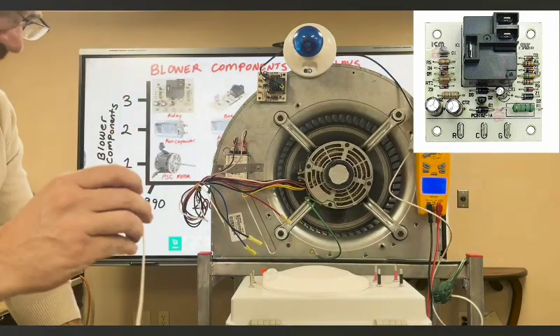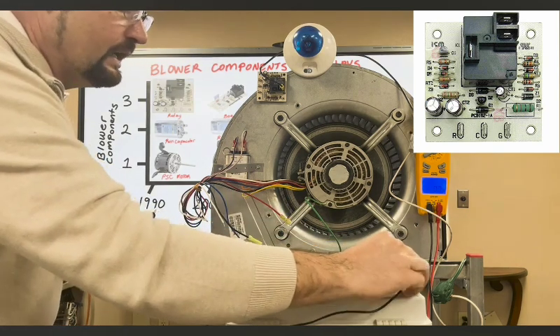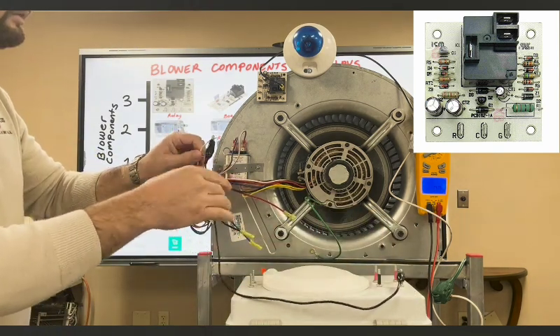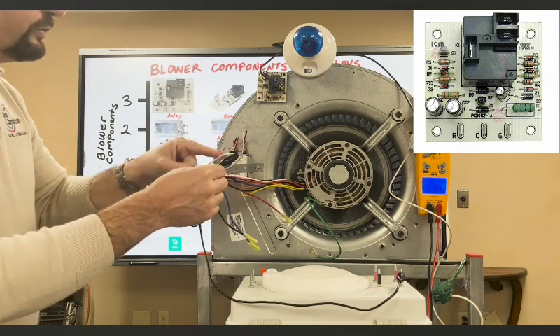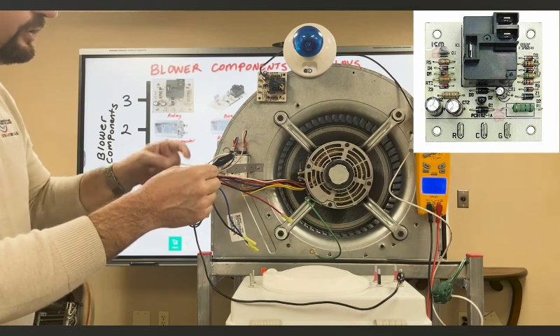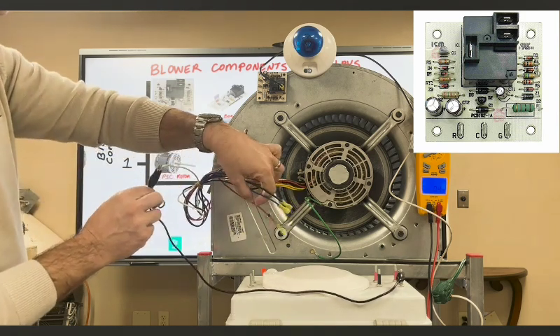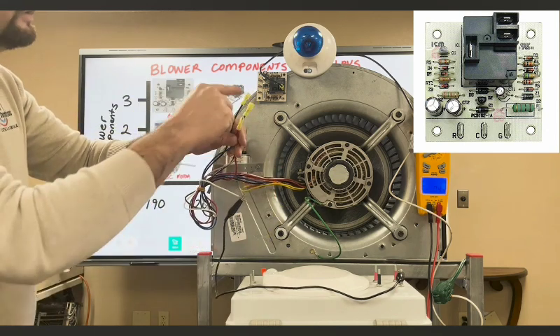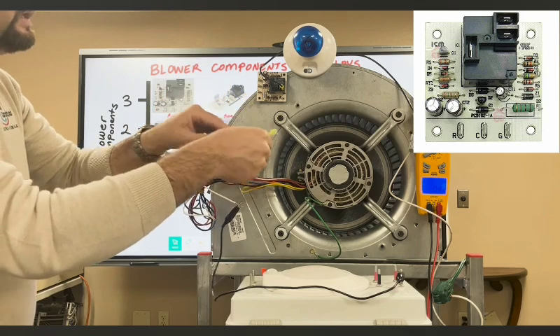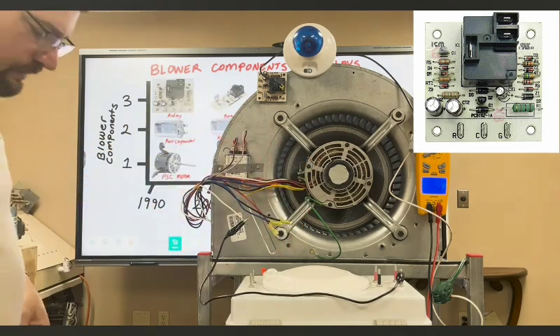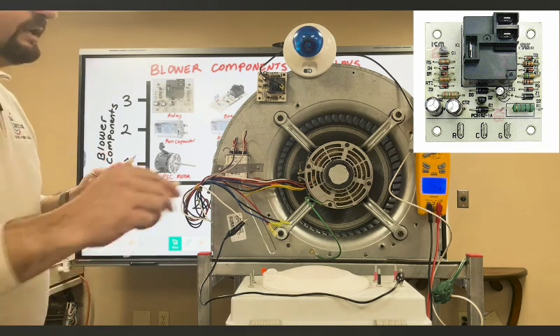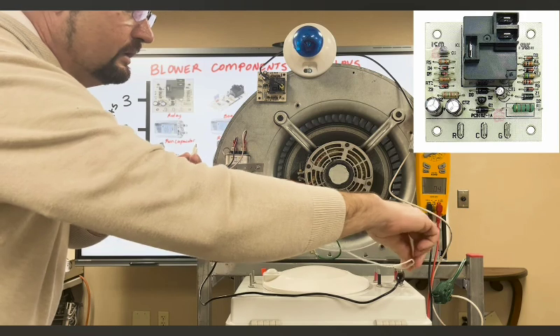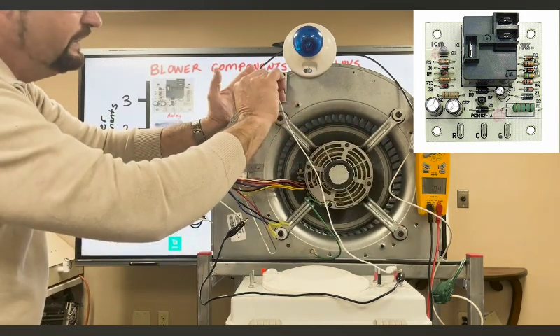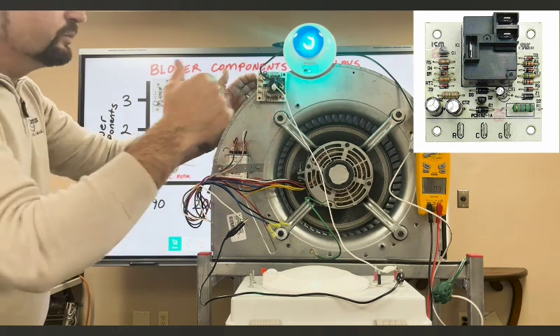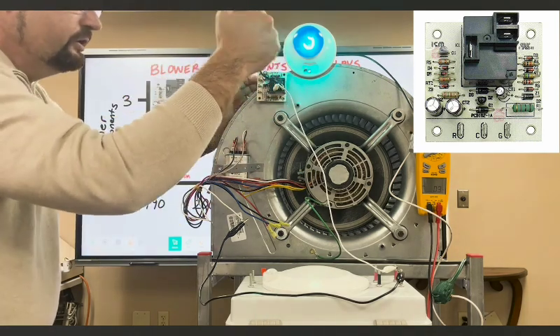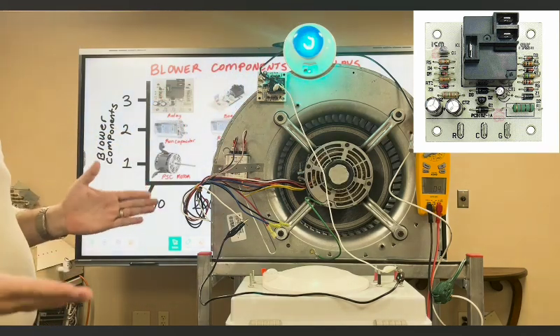Now to wire this up, we're going to take one of our lines and come up to one of our legs on our motor, which is the run winding, which has our capacitor, all that wired through to that. I have 3 other speeds that will receive power on one of these other legs. I can plug any one of these into my board, and I will have power, giving me my 220. Now I'm going to take the second leg of power, which I haven't utilized yet, and run it up to common. You'll see the light will come on because it's normally closed. So we forced power across to the load. So right now we are in a normally closed position, so we have a light.